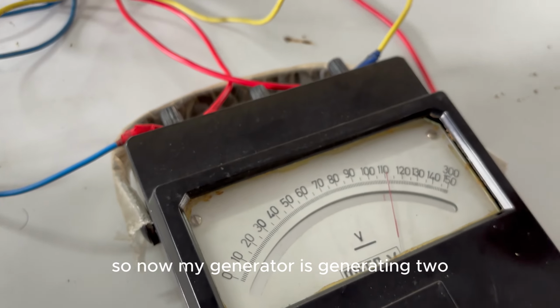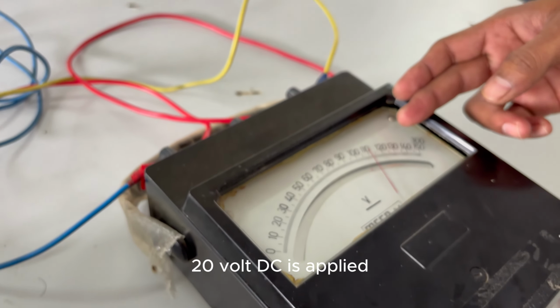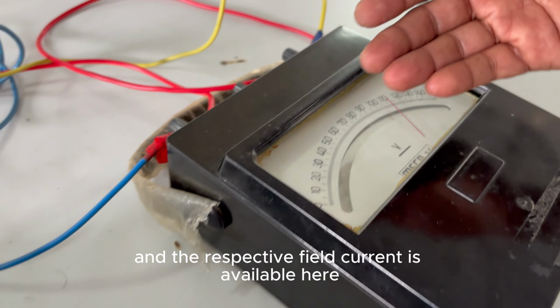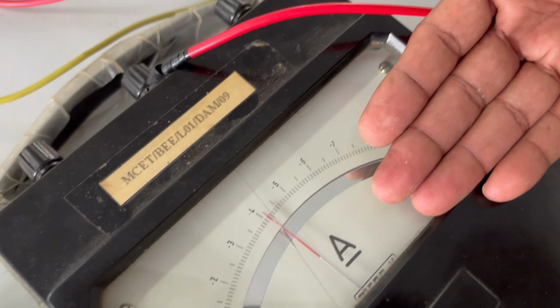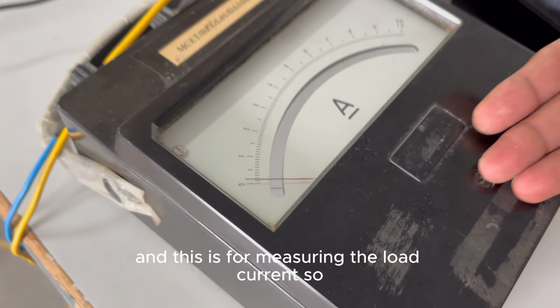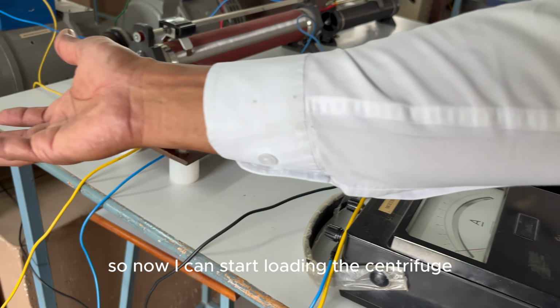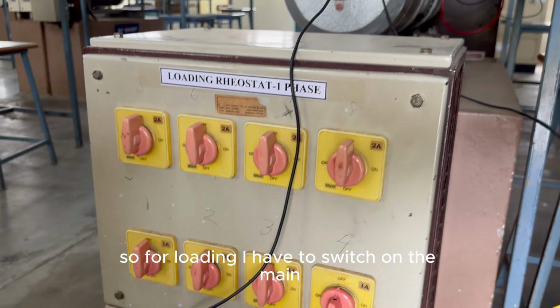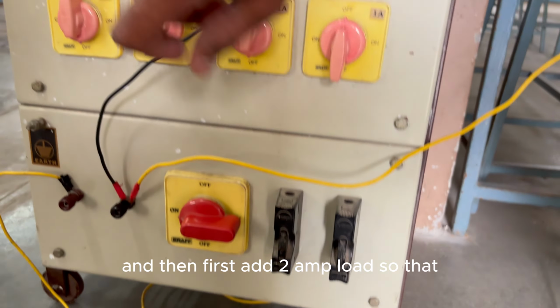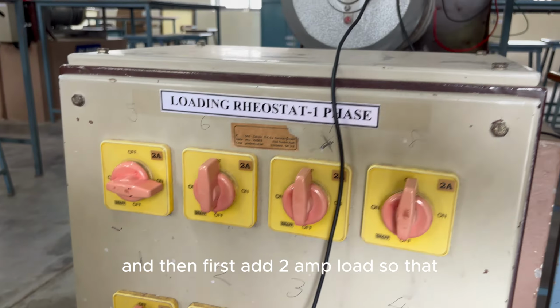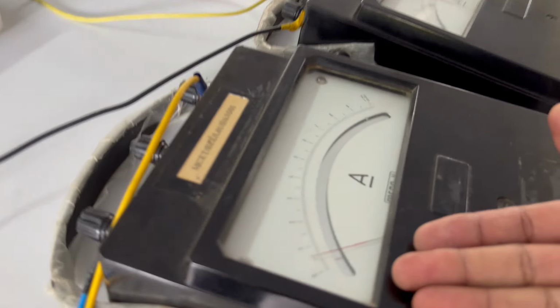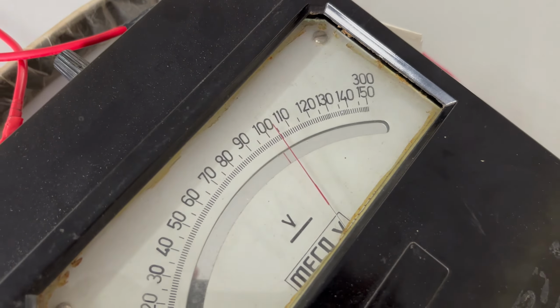Now my generator is generating 220 volt DC supply, the respective field current is available here, and this is for measuring the load current. So now I can start loading the generator. For loading, I have to switch on the main and then first add 2 amp loads, so that the change in current and change in voltage can be noted.